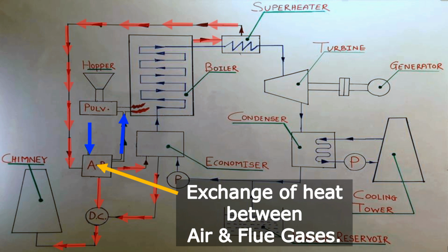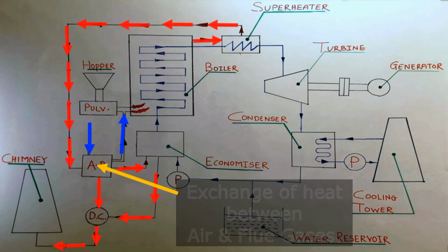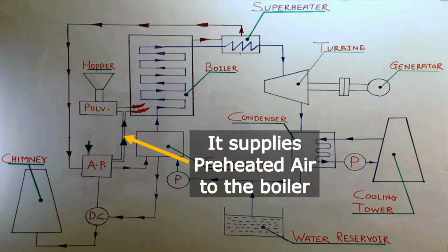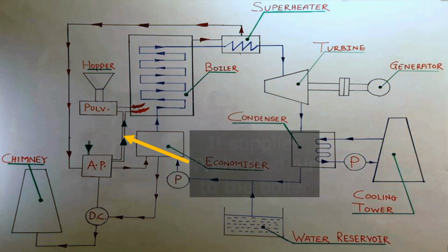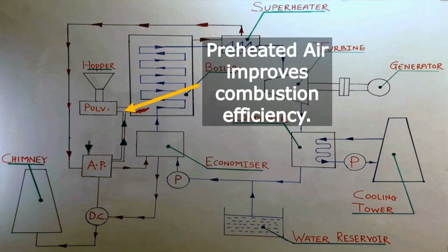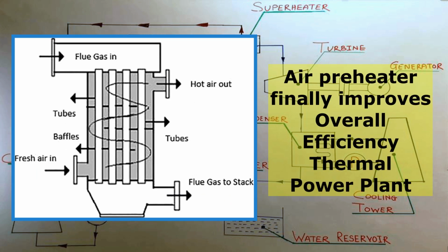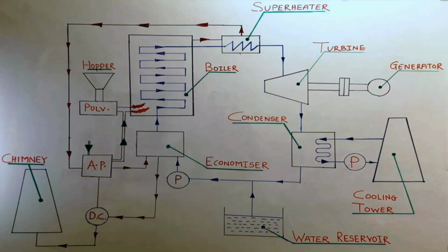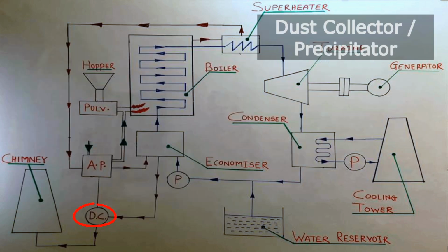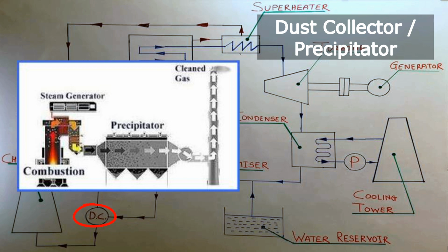Therefore, when the air preheater supplies the surrounding air, it is already heated to a certain temperature that is above atmospheric temperature. Hence, it requires less fuel for the combustion process, and therefore it improves the overall thermal efficiency of the thermal power plant. Now the next element is a dust collector, which is also called a precipitator.